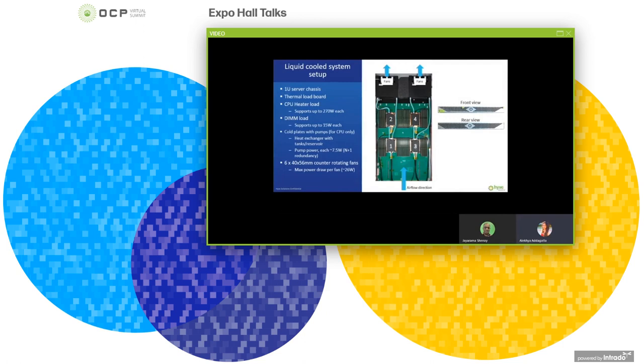Liquid-cooled system setup. I've used a 1U chassis to house the load board, liquid cooling modules, and fans, and used foam to bypass any airflow. For this system, I've used 6 fans, 3 for each liquid cooling module, to provide the necessary airflow. 1, 2, 3, 4 represent locations for heaters and attached thermocouples for the case to measure temperatures.